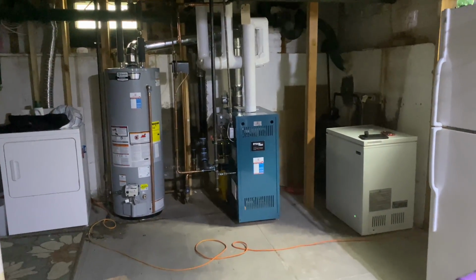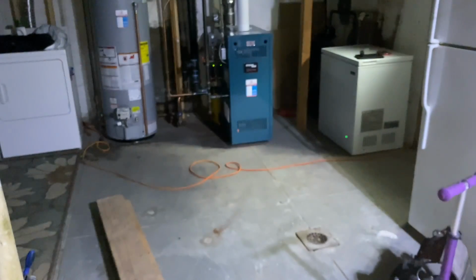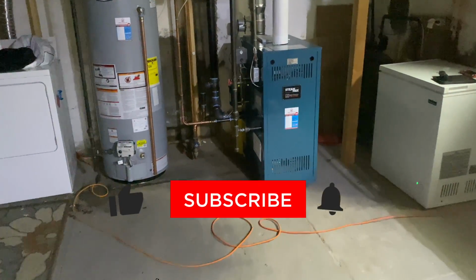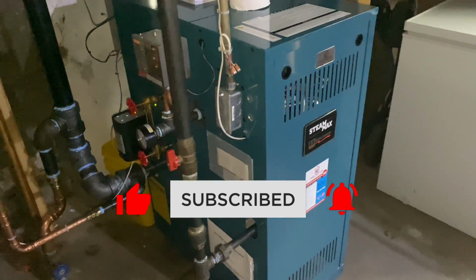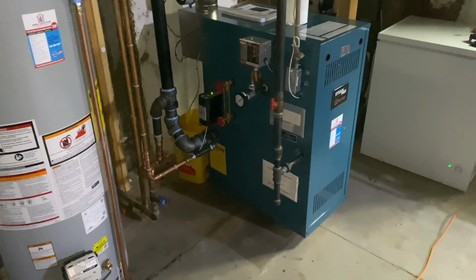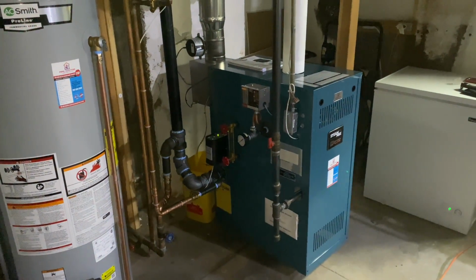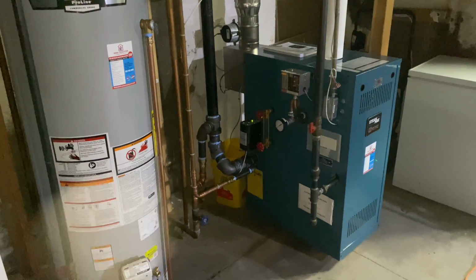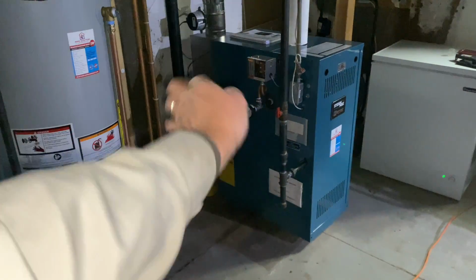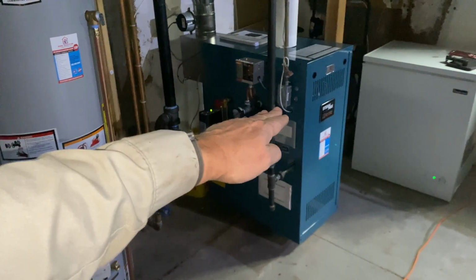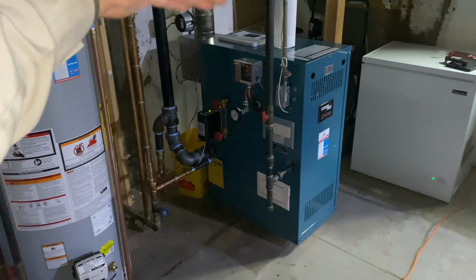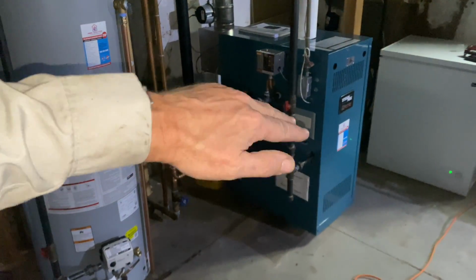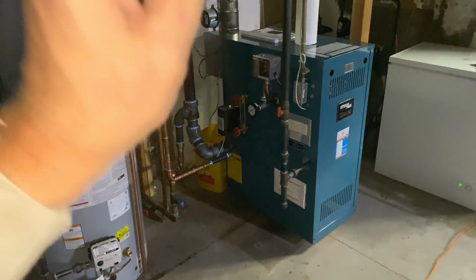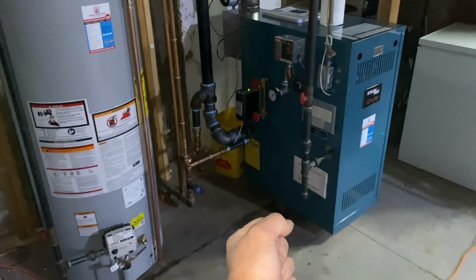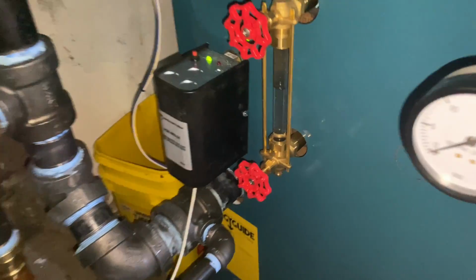All right, ladies and gentlemen, 12:20. It's time to show off. US Boiler SteamMax. It's the STMX 100,000 BTU gas-fired steam boiler. This is far superior than the previous generation, the Independence. We have a larger steam chest. Our steam chest does not contain the heat transfer pins like the previous generation does. Those heat transfer pins are removed in the steam chamber, and we have more heat transfer pins where steam generation occurs, which is below the waterline.